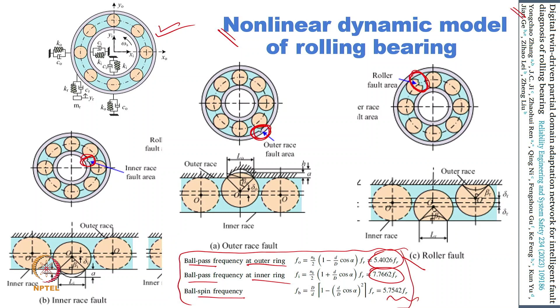And this is what we already covered in one of our lecture slides: the ball pass frequency at the outer ring, the ball pass frequency at the inner ring, and the ball spin frequency, with the relations given here. You can see the maximum frequency will be when there is a failure at the inner ring, and the minimum frequency value will be when there is a failure at the outer ring, and in between is the ball frequency, for a failure of the ball. So these three have been shown here.